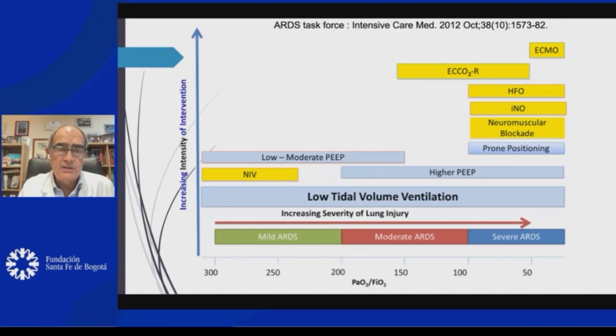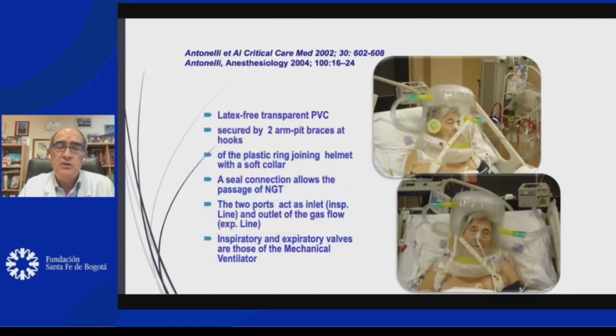So what was indeed pragmatic, represented by our action, was the possibility of using this technique in various conditions. We will refer specifically to the use of the helmet. The helmet is a latex-free transparent PVC hood that is secured to the body through two armpit braces. And there is a plastic ring that joins the helmet with a soft collar, and the seal connection through which you can pass an NG tube.